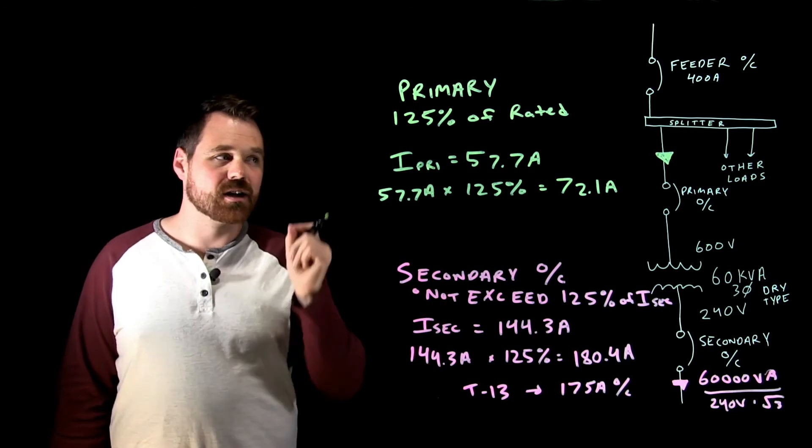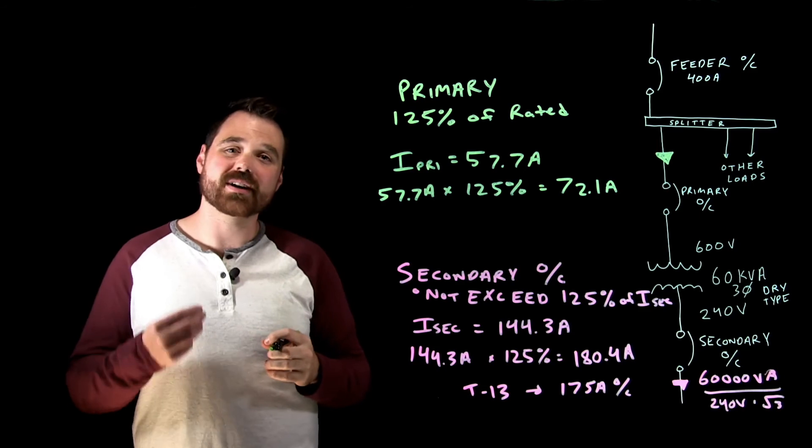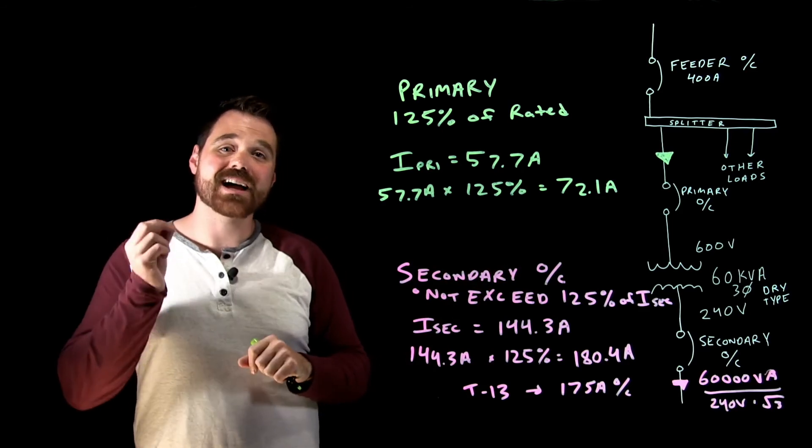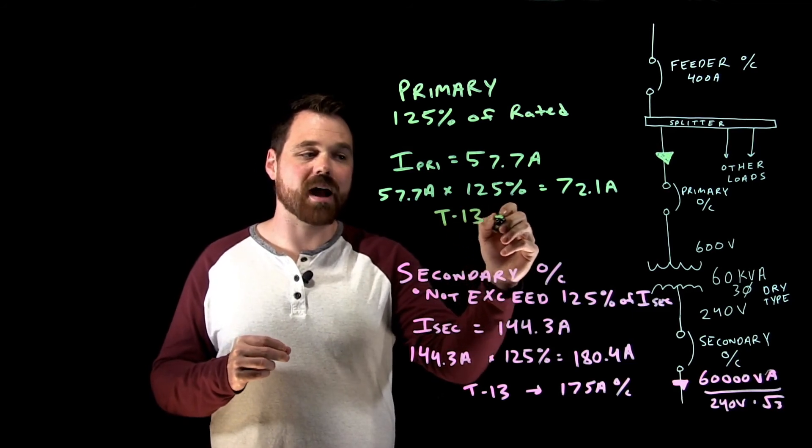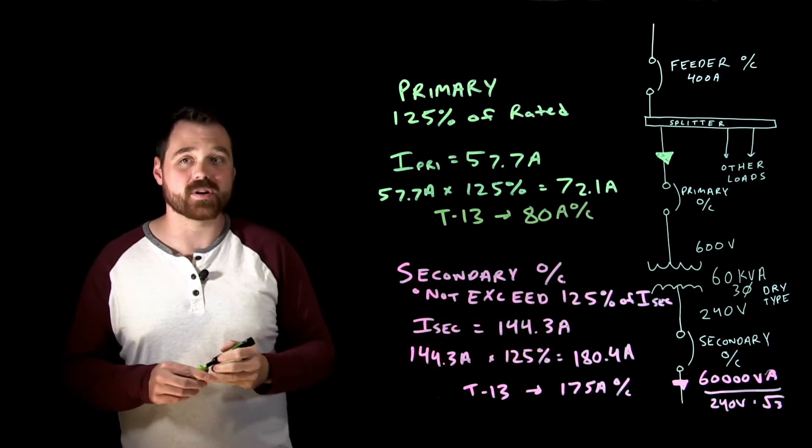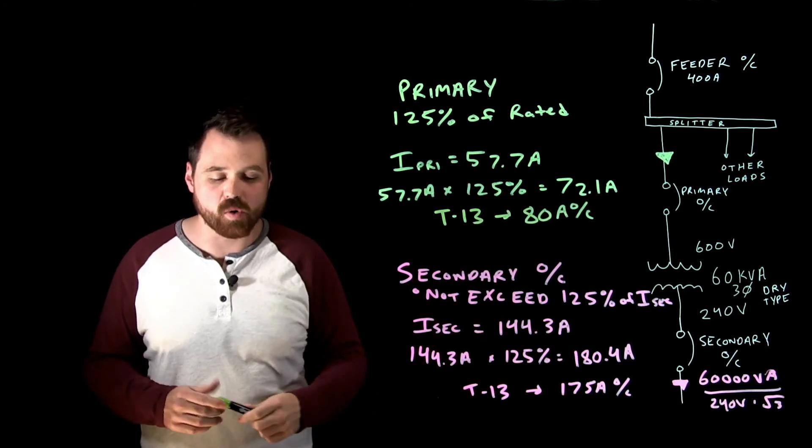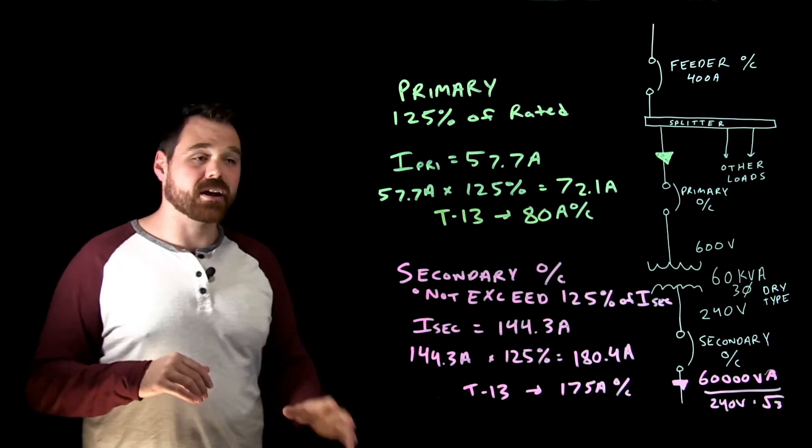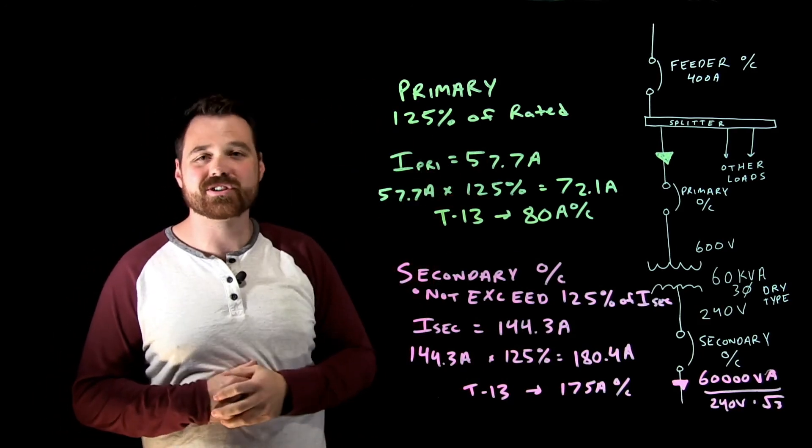Now here's the trick. The rule does tell us you cannot exceed 125 percent of the rating meaning I cannot exceed 72.1. But a few sub rules later it tells us if 125 percent of the rating of the overcurrent device is not available, the next higher size shall be permitted. So in this case on table 13 we're actually permitted to go up to an 80 amp overcurrent device. It's very different - with the secondary we were not permitted to go up, with the primary we are permitted to go up. If I had no secondary OC at all I would size my primary the exact same way.